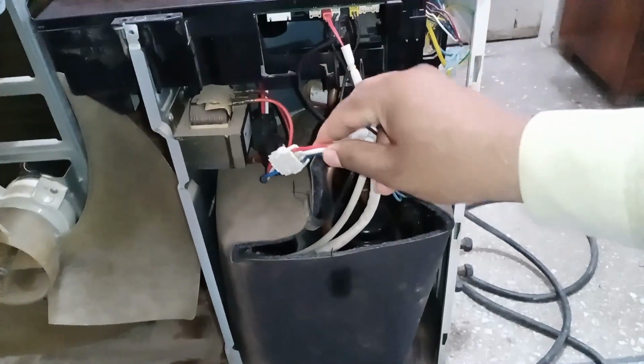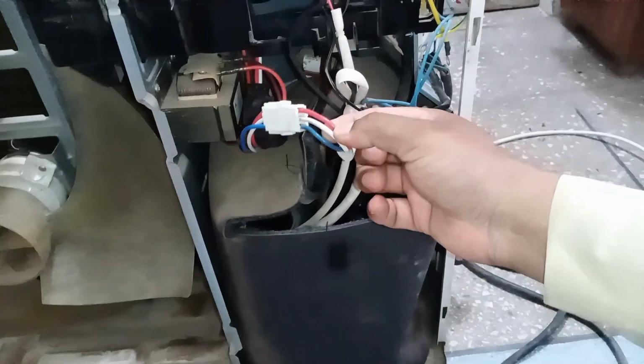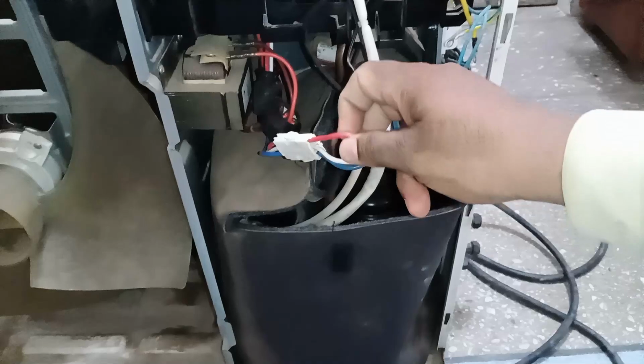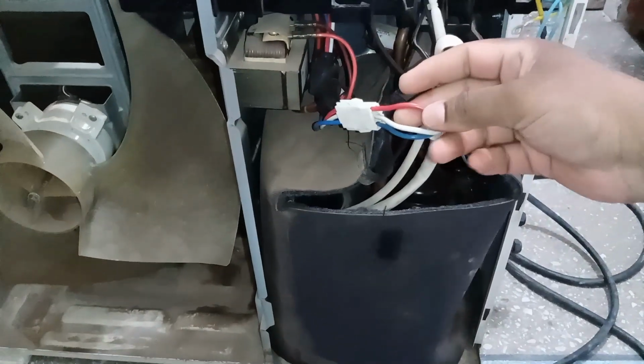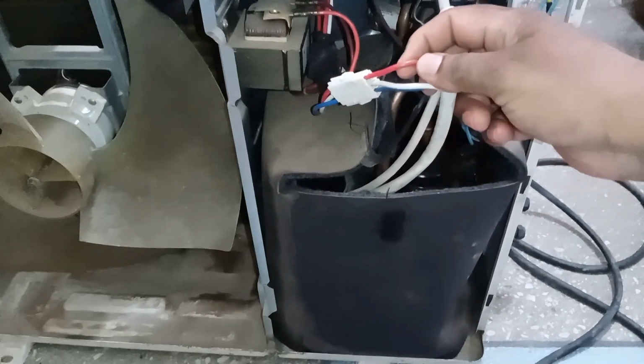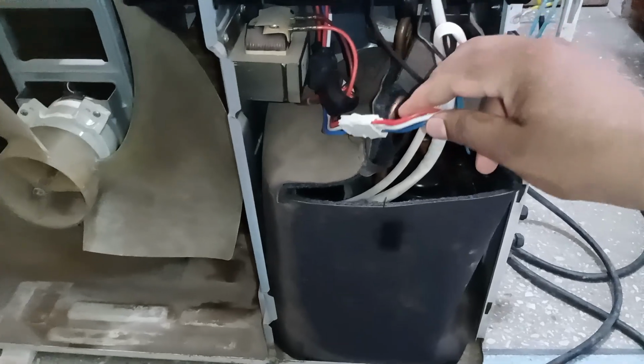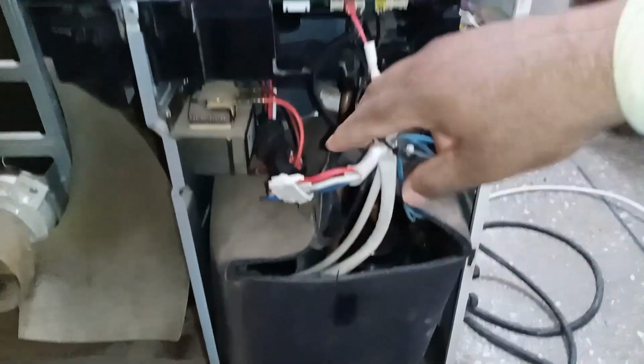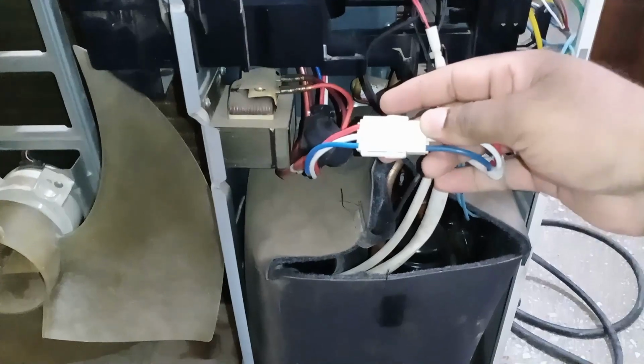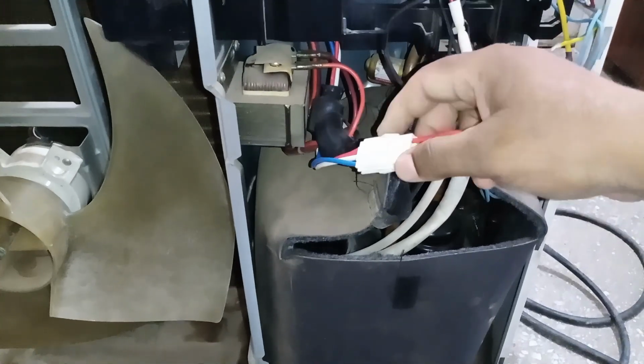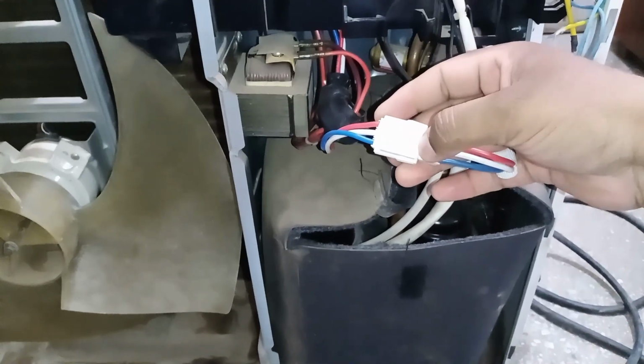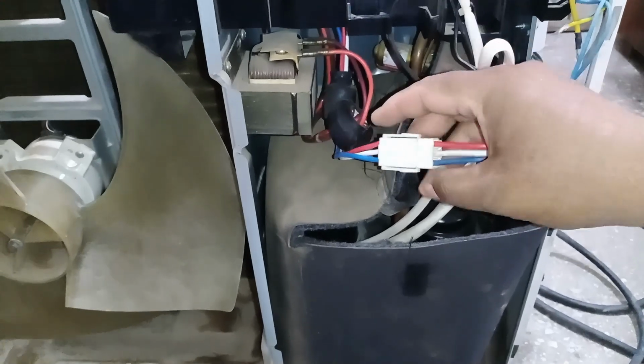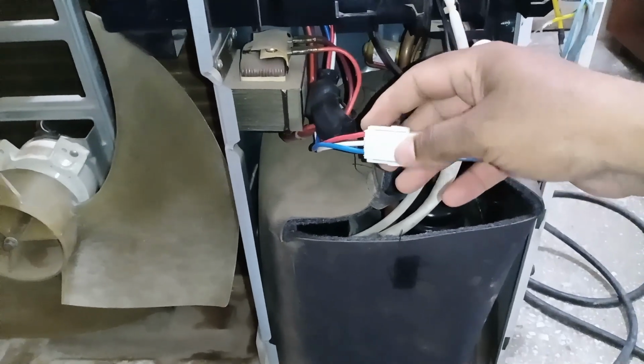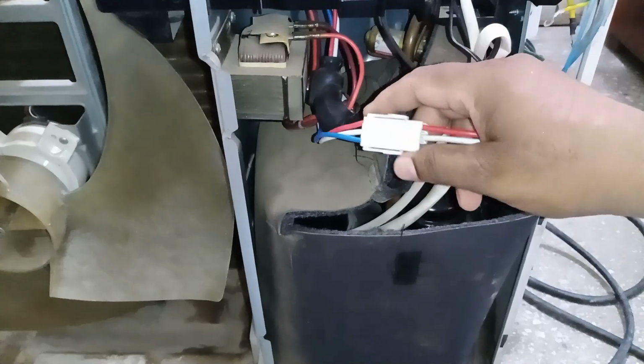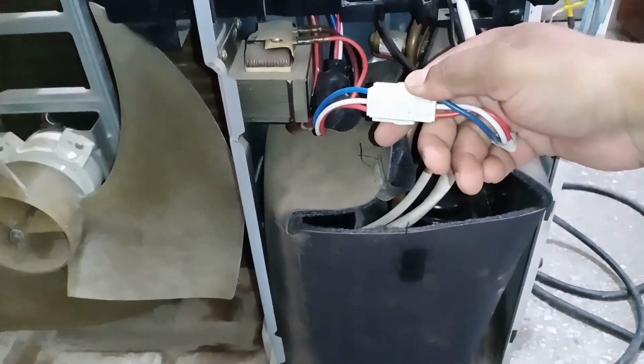If any wire is cut, either due to heat damage or if it gets disconnected, the unit will still display error 19. This could be due to burnt, loose, or broken wires in the outdoor unit's PCB or compressor circuit. Now let's continue diagnosing further to pinpoint the exact cause of this error. If the connector in the outdoor unit becomes loose, the unit may lose proper electrical contact, leading to error 19. If there is rust on the connector pins, it can cause a weak connection, triggering the error.